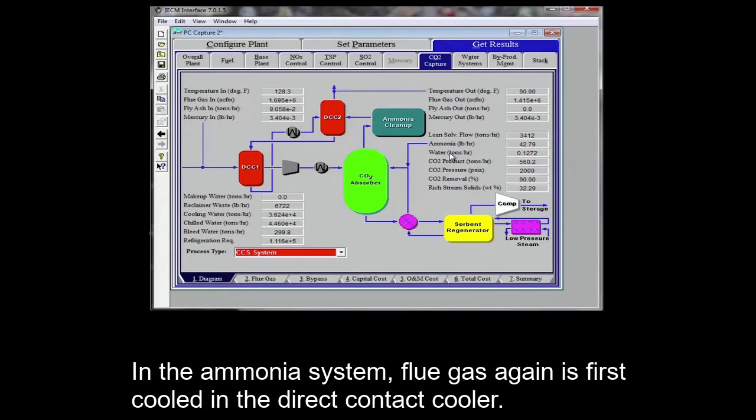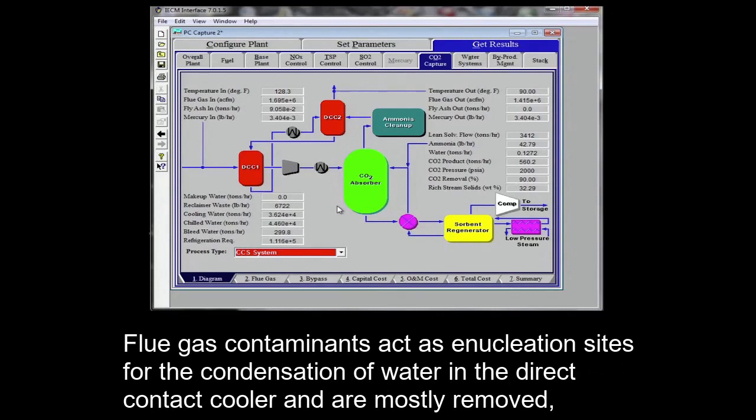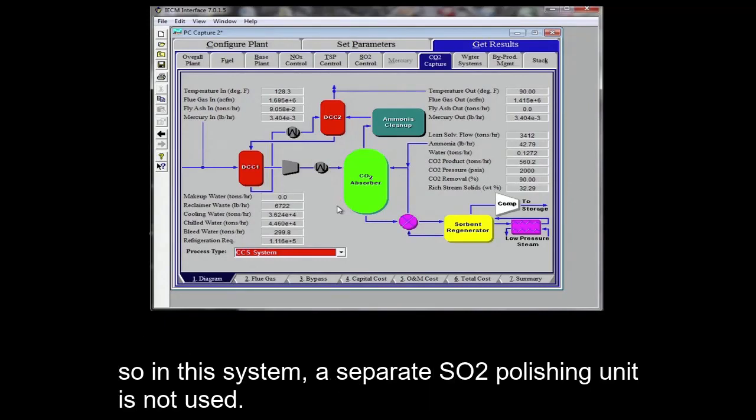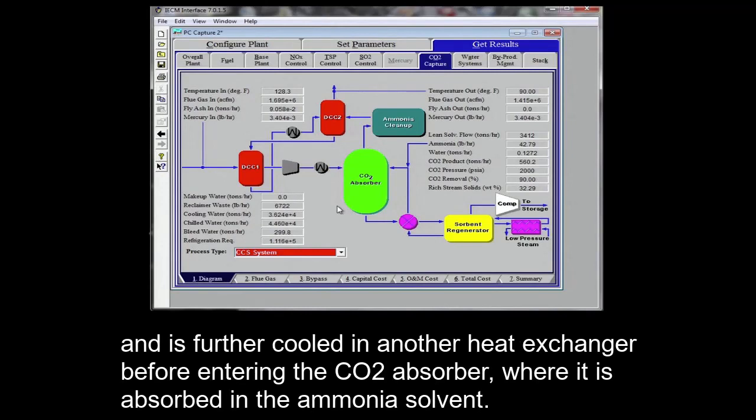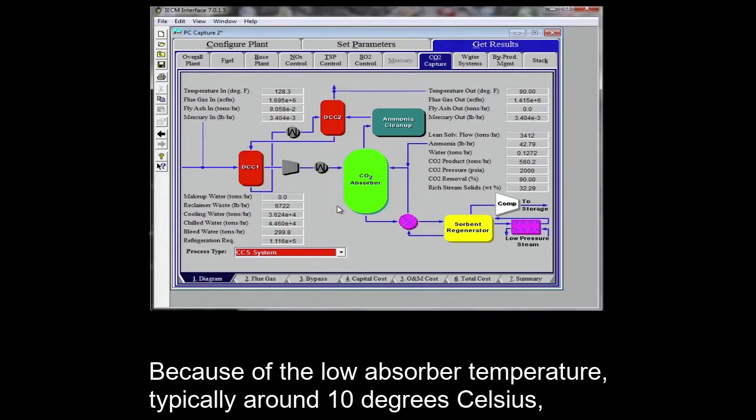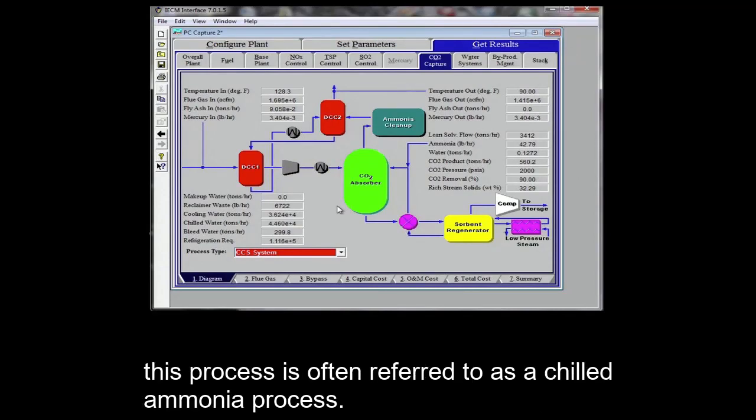In the ammonia system, flue gas again is first cooled in the direct contact cooler. Flue gas contaminants act as a nucleation sites for the condensation of water in the direct contact cooler and are mostly removed, so in this system a separate SO2 polishing unit is not used. The flue gas is then compressed to overcome the pressure drop of the system and is further cooled in another heat exchanger before entering the CO2 absorber where it is absorbed in the ammonia solvent.